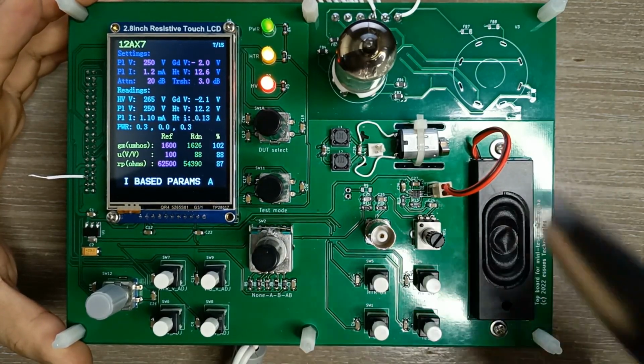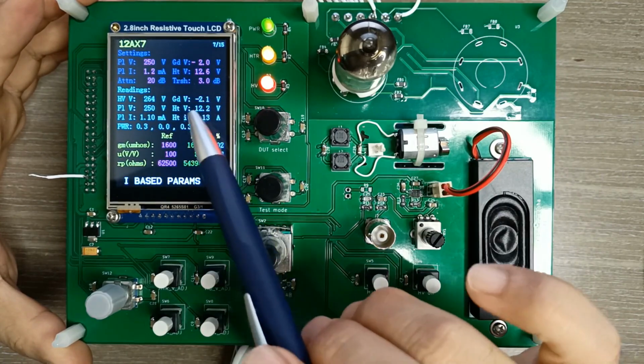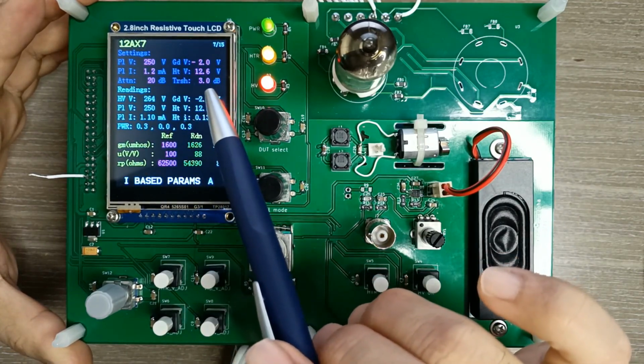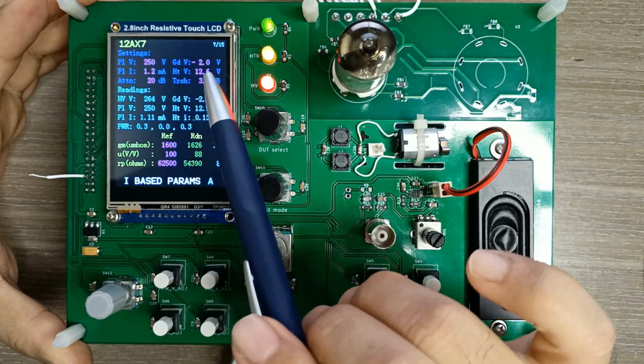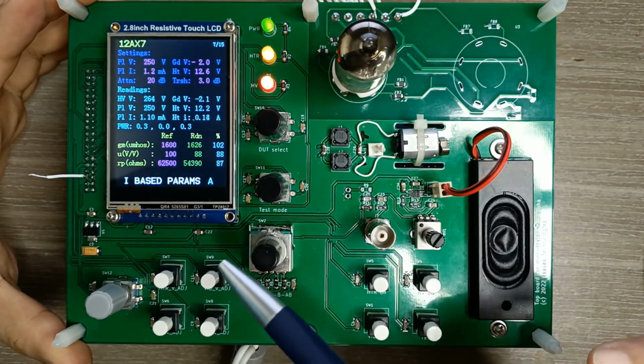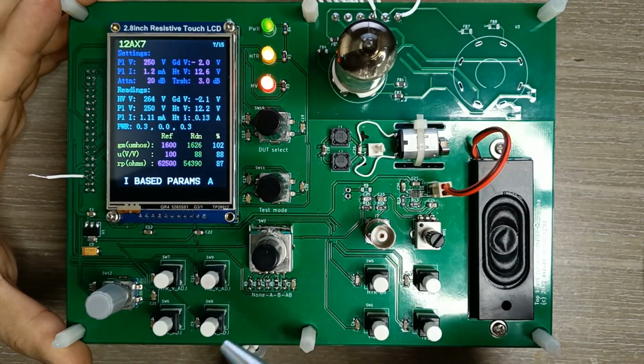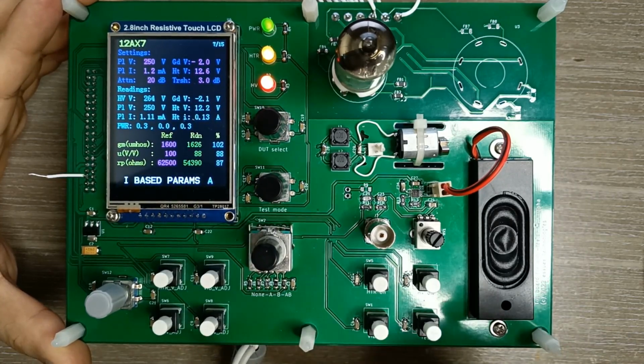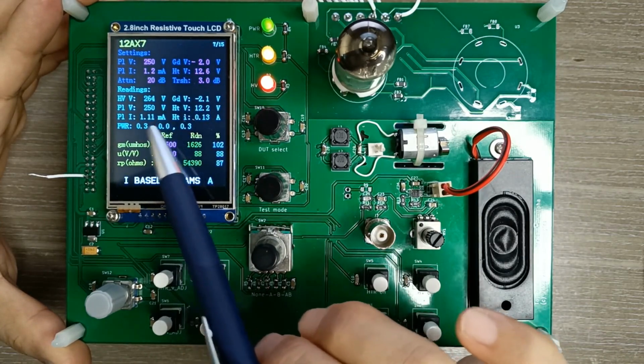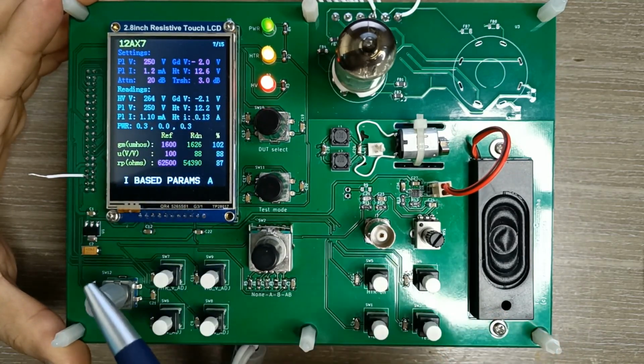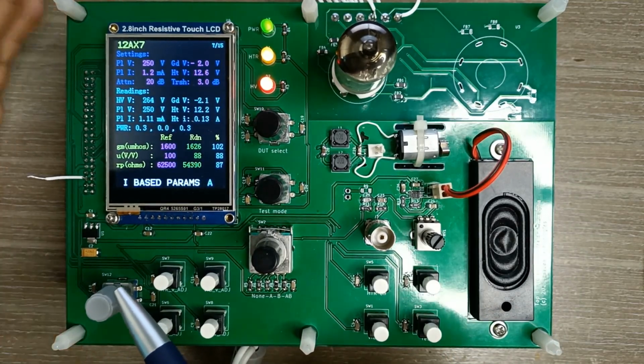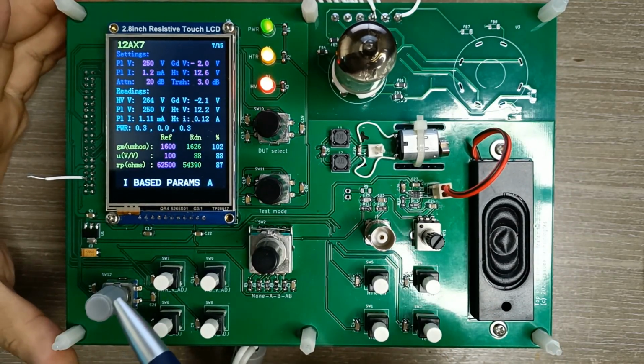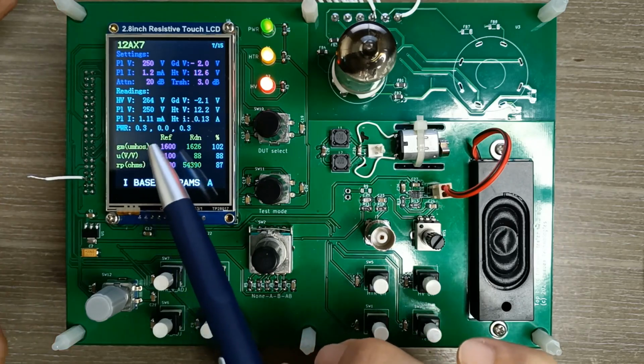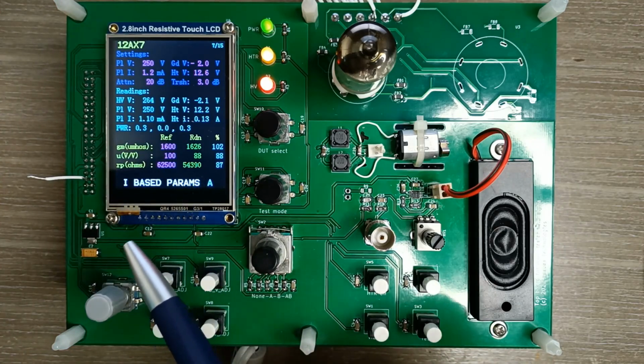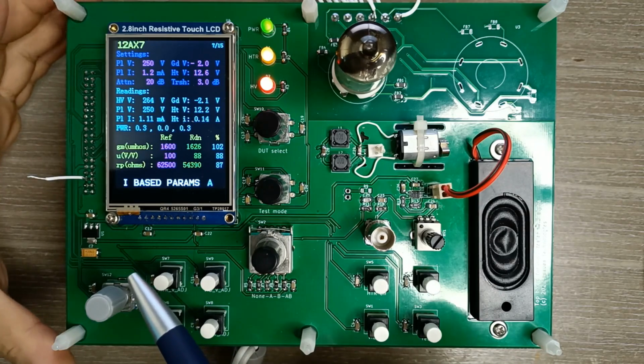Okay, and you probably notice that the reading does not match the setting. There's a 1% or 2% error. It's because this machine is not calibrated yet. So instead of 1.2 milliamp, we can see the reading is only 1.1 milliamp. That's because the constant current source is configured in hardware for 1.2 milliamp, but because it's not calibrated, let's ignore that for a while.